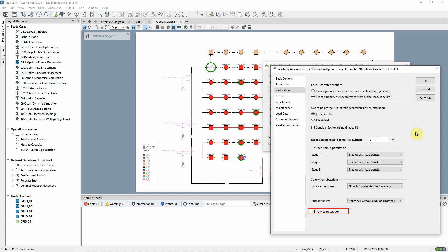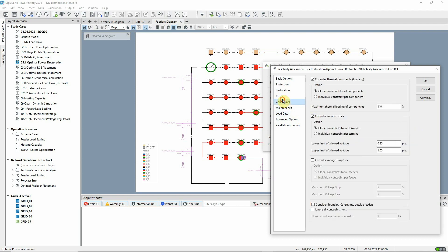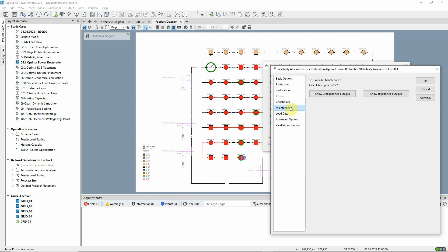And finally, if this option is selected, the restoration uses a more precise algorithm to solve load flow convergence issues during the restoration process, but the calculation can take longer to run as a result. Note that on the Constraints page of the Reliability Assessment command, we've specified that thermal and voltage limits must be observed during the restoration process. In some cases, this can only be achieved through load shedding. And on the Maintenance page, we have selected this option, meaning the assessment will be carried out both for the case where the network is initially intact and for the case where planned outages are taken into account.